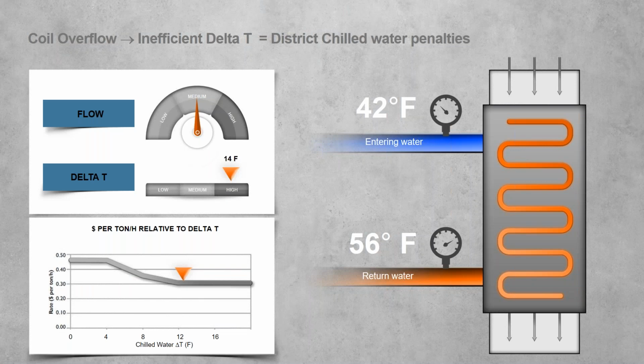We know that coil overflow leads to an inefficient delta T, which in this scenario can and does lead to district chilled water penalties. Here we have a real example we can give, and this is just an example, but referencing some of the numbers from the Nashville buildings we're going to talk about today. On the right side of my screen, I have a typical heat exchanger or a coil. On the top in blue, I have my entering water coming from my district chilled water plant at 42 degrees, passes through my heat exchanger or coil, takes a nice heat transfer, and leaves the return at 56 degrees in this scenario, or a 14-degree heat transfer.